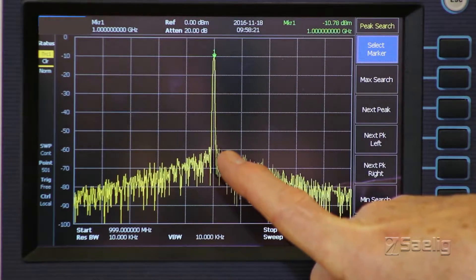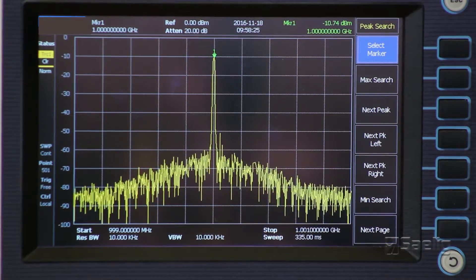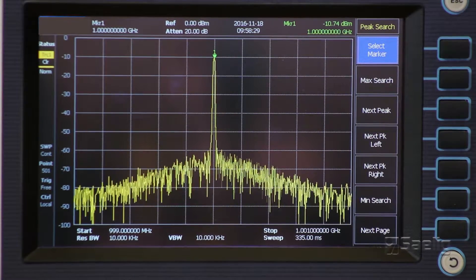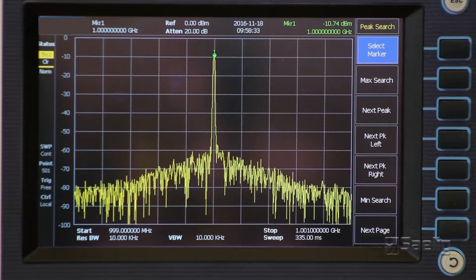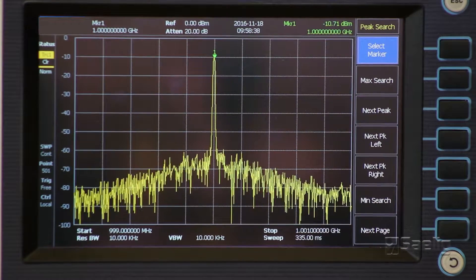So what we have here is the one gigahertz frequency coming out, and the level is about minus ten point seven four, so about minus eleven dBm. That's approximately what you're supposed to get out of this device with the factory default settings.